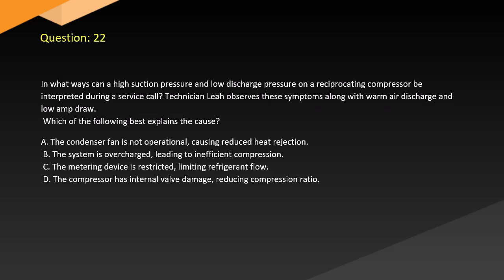Question 22. In what ways can a high suction pressure and low discharge pressure on a reciprocating compressor be interpreted during a service call? Technician Lee observes these symptoms along with warm air discharge and low amp draw. Which of the following best explains the cause?